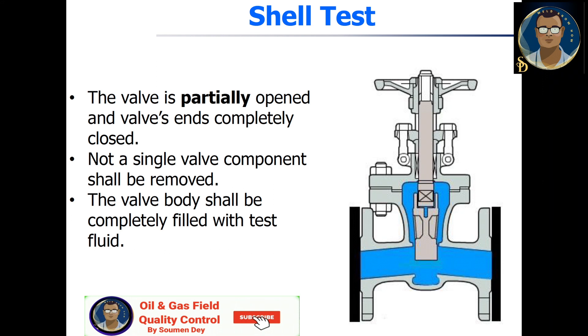For the shell or body test, the valve is partially opened and valve ends completely closed. Not a single valve component shall be removed. The valve body shall be completely filled with test fluid and then pressure will be applied to check whether the body or shell has any leakage or not.